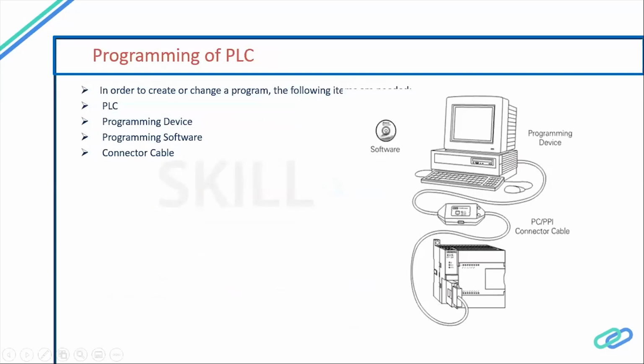For a PLC program, you need to connect. There are different types of communication protocols to interface with a PLC. Some PLCs have proprietary protocols, so you need to use a proprietary communication cable and a proprietary OPC or communication driver. And some are open, just like the example I'm giving you, a Schneider PLC. You need to buy only the software. You use a normal Ethernet cable to interface directly with the PLC and start your program or software development. A SCADA developer can also do the same communication without any third party protocol. All the communication protocols are inbuilt in your SCADA and PLC software. If it's third party, you need to buy programming software and connector cables.